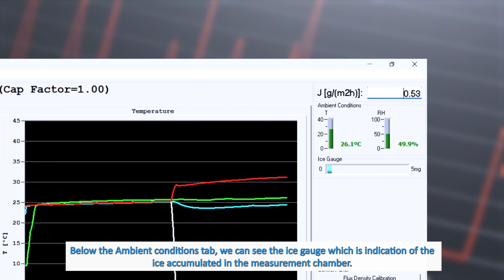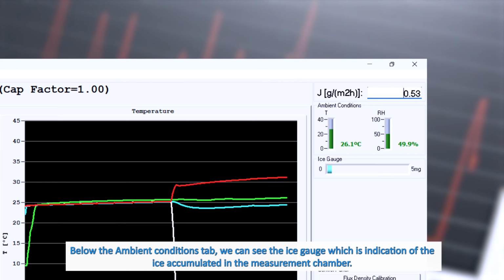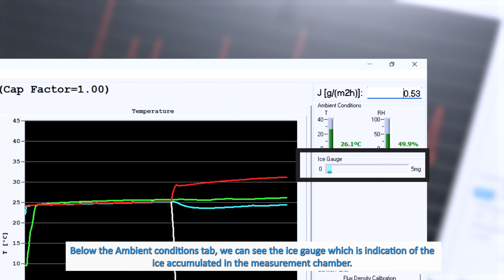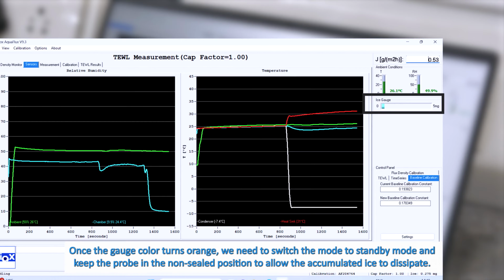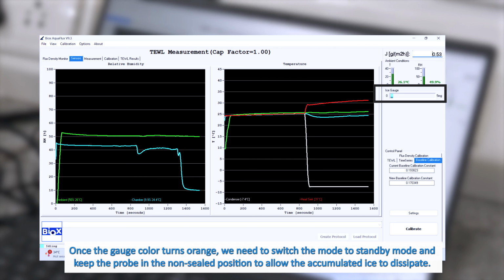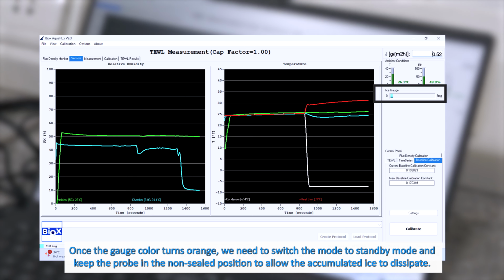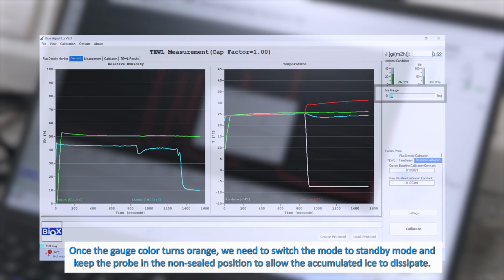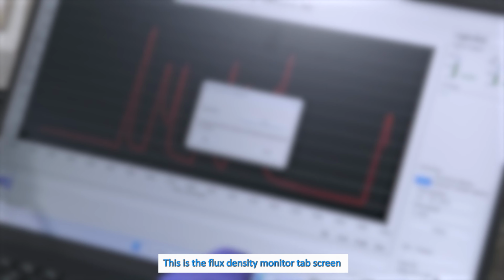Below the ambient conditions tab, we can see the ice gauge, which is an indication of the ice accumulated in the measurement chamber. Once the gauge color turns orange, we need to switch the mode to standby mode and keep the probe in the non-sealed position to allow the accumulated ice to dissipate.